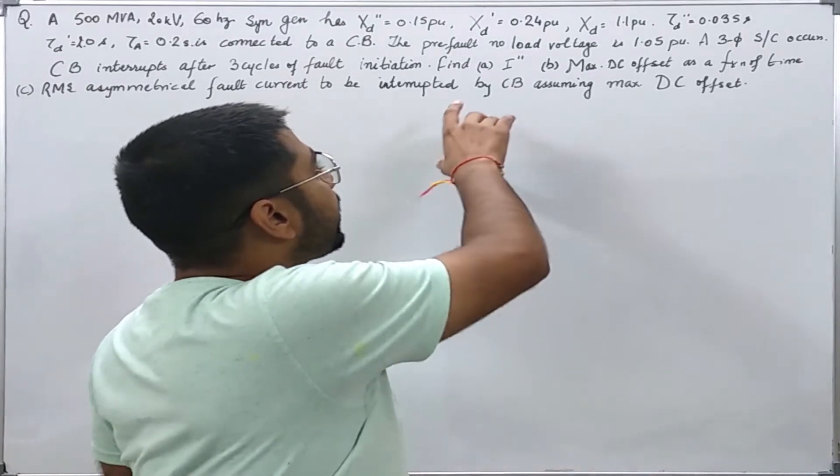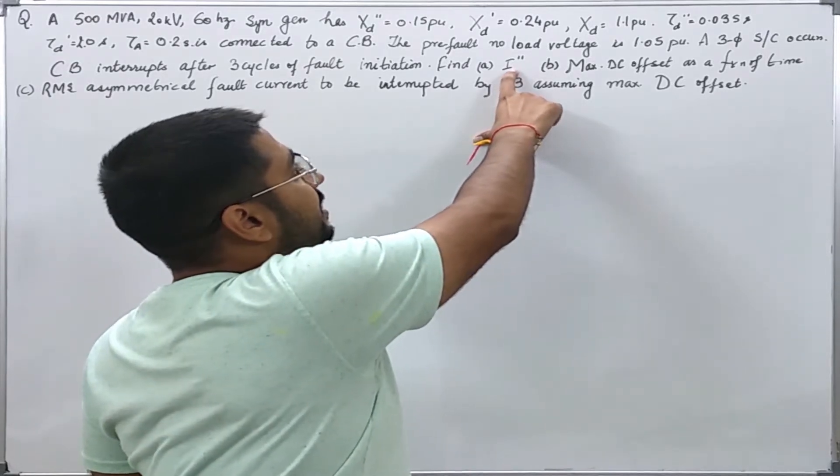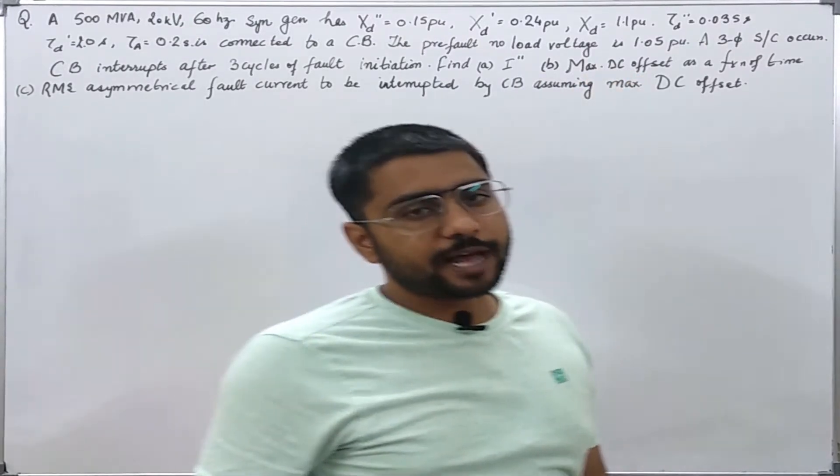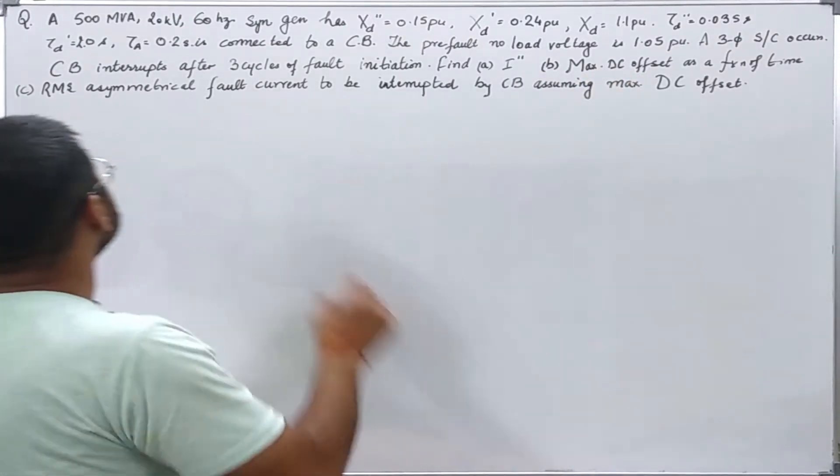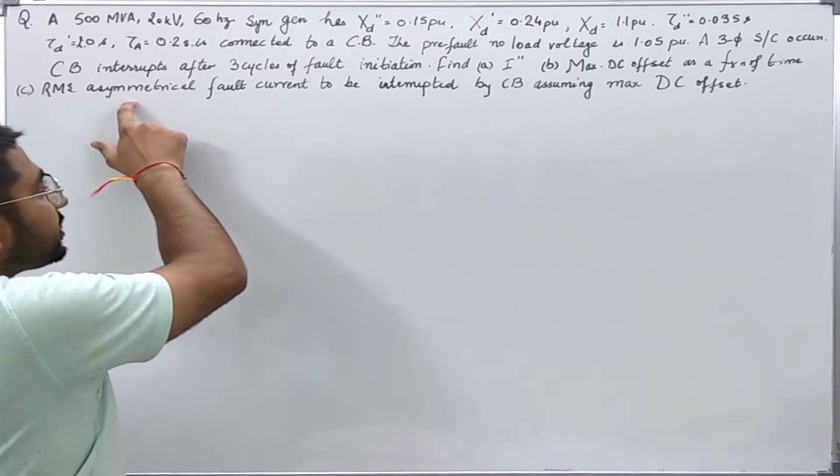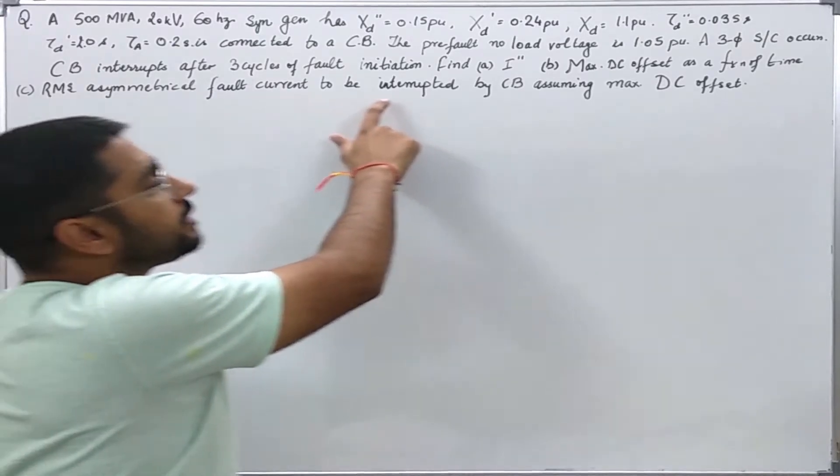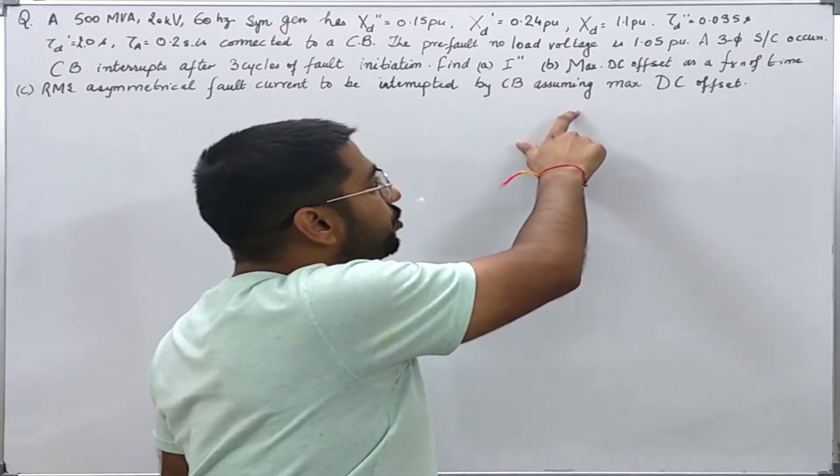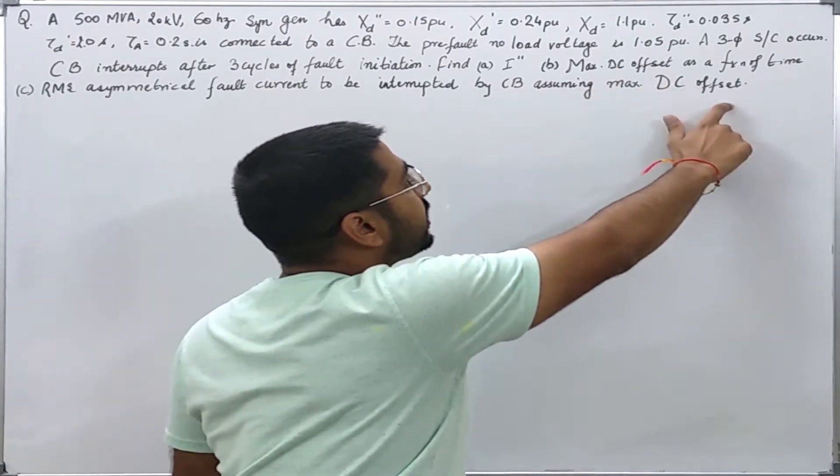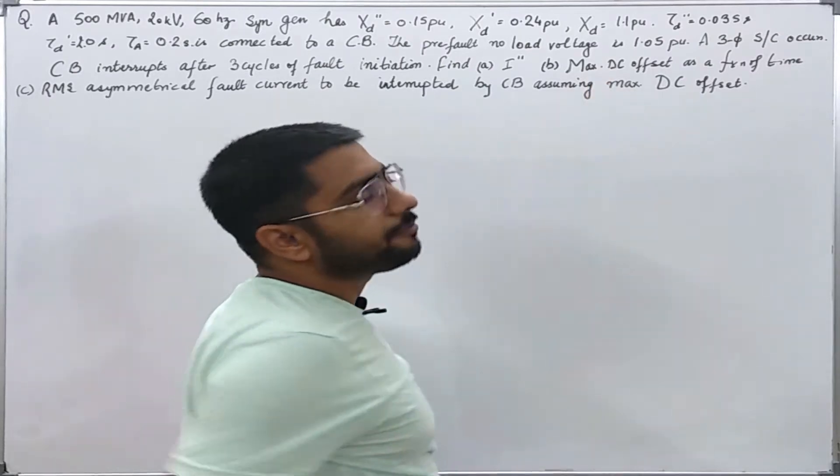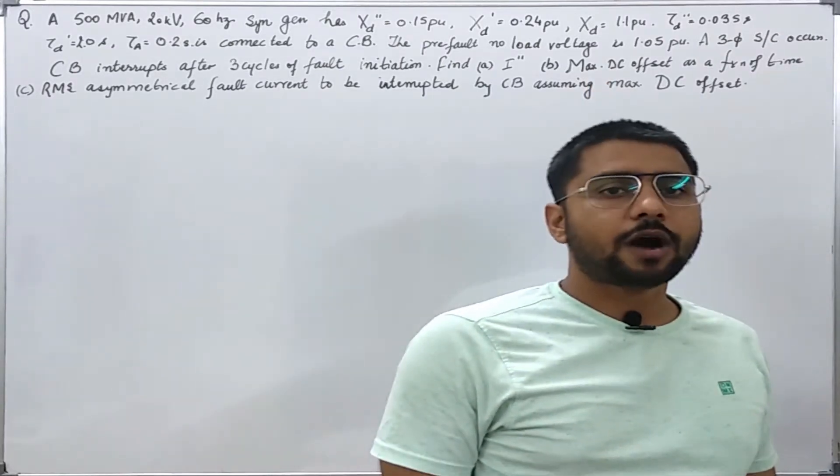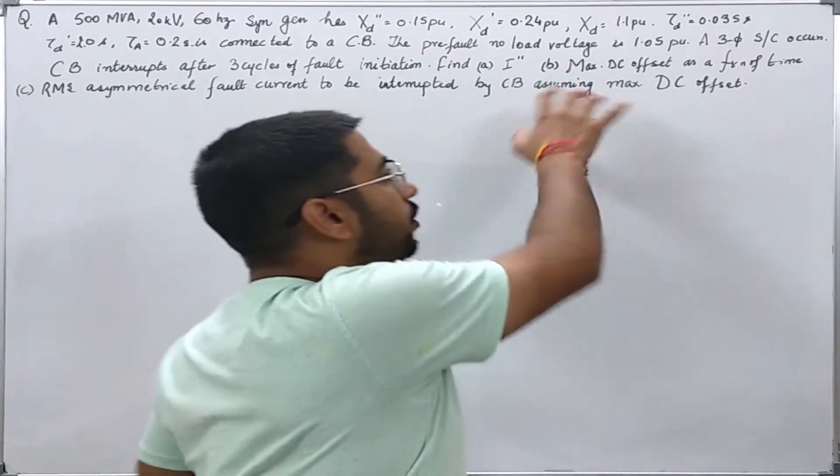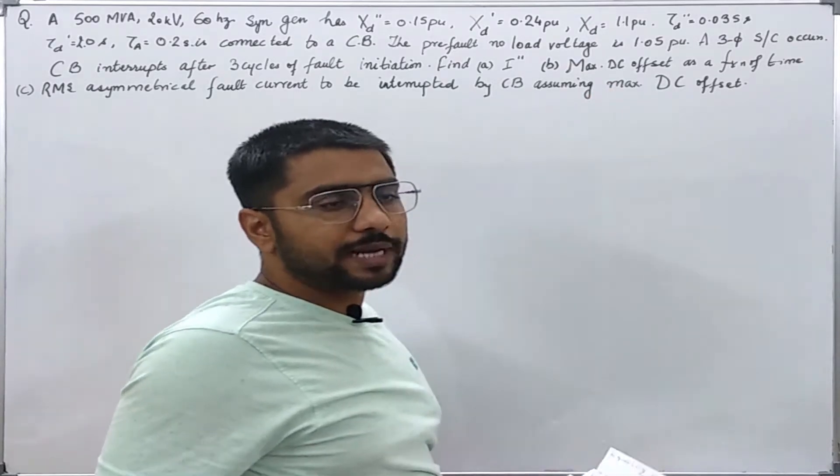So what we are asked? We are asked to find the sub-transient fault current, the maximum DC offset as a function of time, and the RMS asymmetrical fault current which will be interrupted by the circuit breaker assuming that the DC offset is having the maximum value. So let us see how to solve this numerical, and this will cover all the concepts we have studied in our previous two lectures.